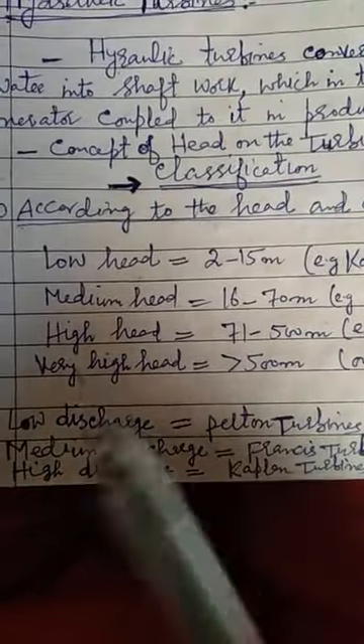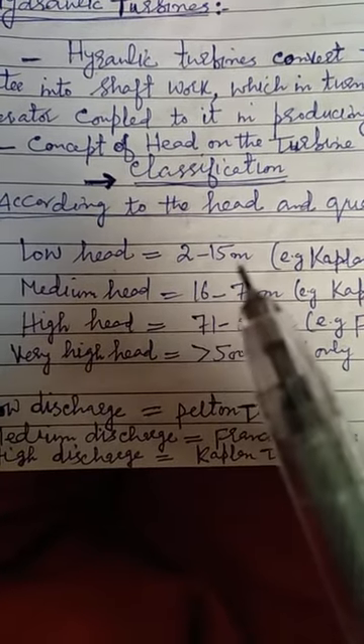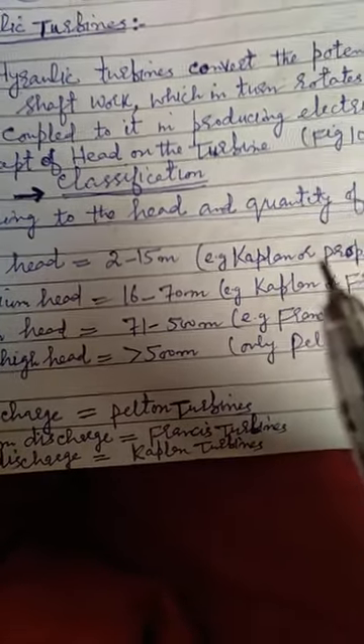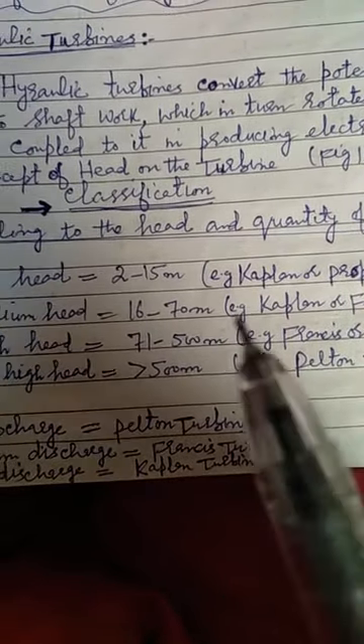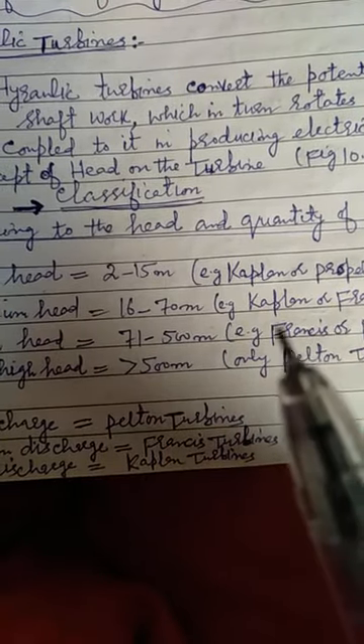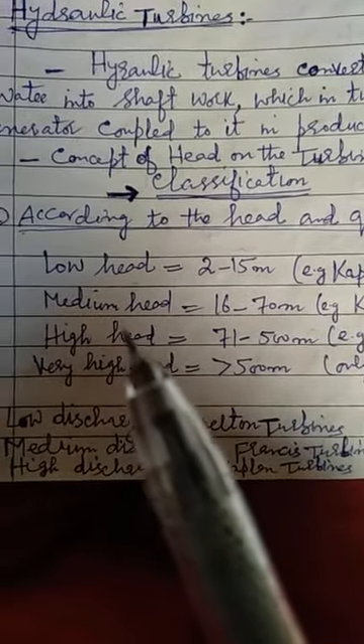Based on head, there are low head turbines with a head range of 2 to 15 meters. For low head turbines, the example is the Kaplan or propeller turbine. We will discuss these in more detail later. There is also a medium head turbine with a head range of 16 to 70 meters, and the example is the Kaplan or Francis turbine.